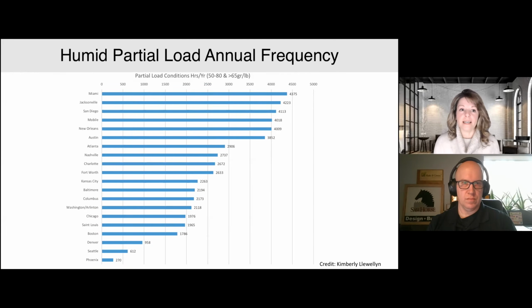So a friend of mine, Kimberly Llewellyn from Mitsubishi, put this graph together, and it really shows, when we're looking at applying ventilation and thinking about how we're going to handle the moisture from that ventilation, the hours of the year that these areas are in partial load times. So even Miami has 4,300 hours of the year in partial load conditions. We're bringing in ventilation air, but we're potentially not running our air conditioner enough to handle those moisture loads. So she's got it all over the place.